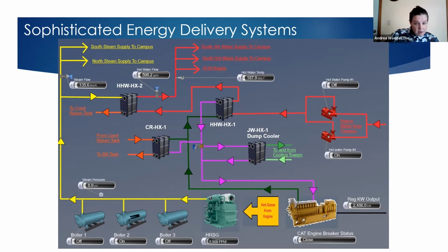So you've got steam coming out of the HRSG, the heat recovery steam generator, and then we've got the boilers to supplement that. So your campus electrically can be anywhere from 2 megawatts to 8 megawatts on demand. And for the steam side, it could be anywhere from 4,000 or 5,000 pounds per hour of low pressure steam to as high as 30,000 pounds per hour. That steam is being used for hot water, heat, process, humidification, all kinds of needs in the campus.